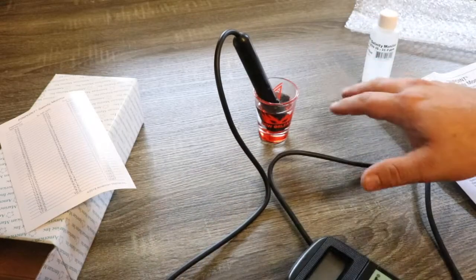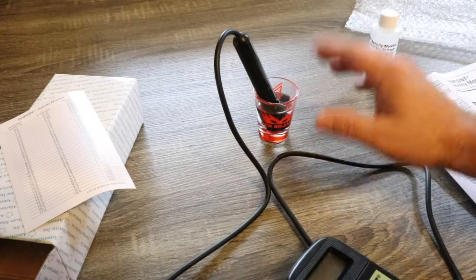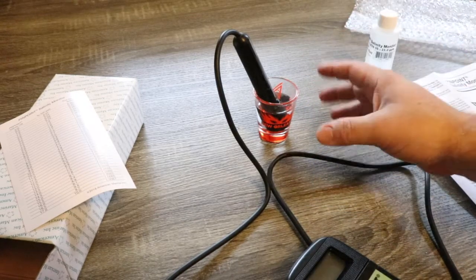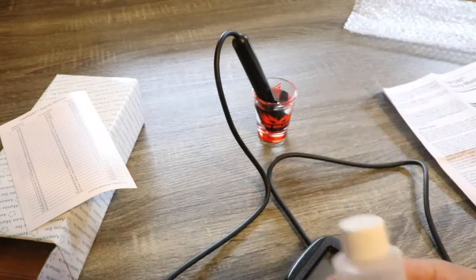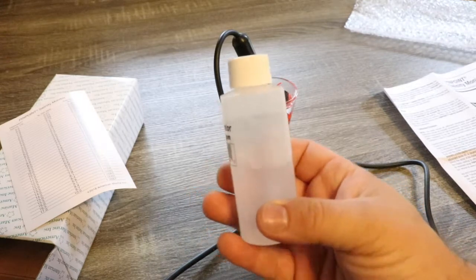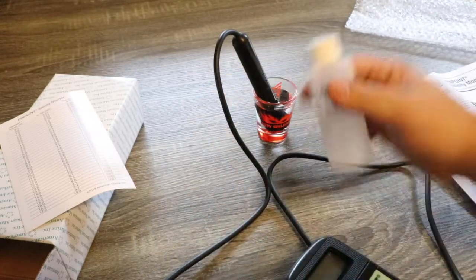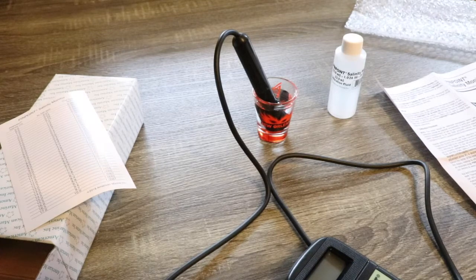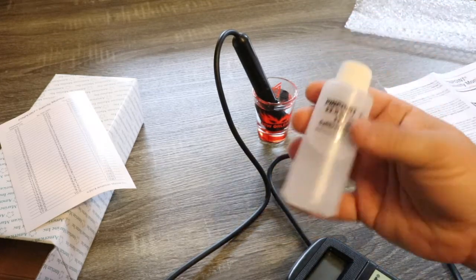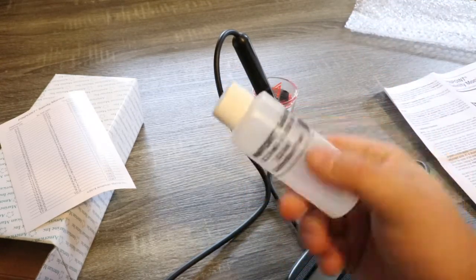All right, so we have the probe and it's important to make sure that the probe has time to get to the same temperature. Using the shot glass, we used up about half of the calibration fluid. Depending on how you go about doing this, you're going to get at least two calibrations from this one bottle. This stuff isn't that expensive either, it's pretty inexpensive.